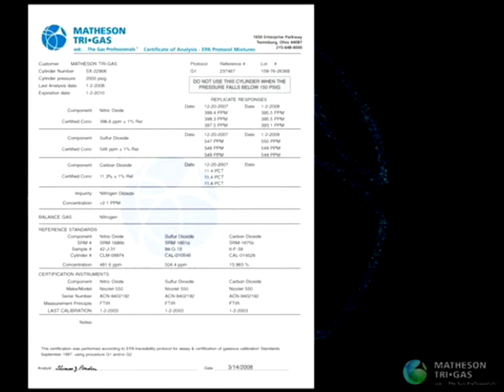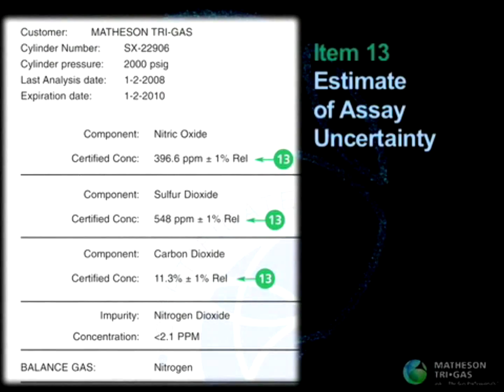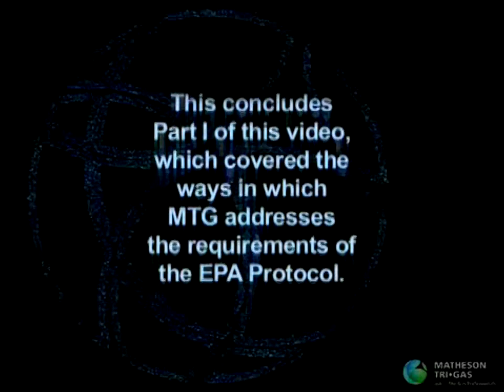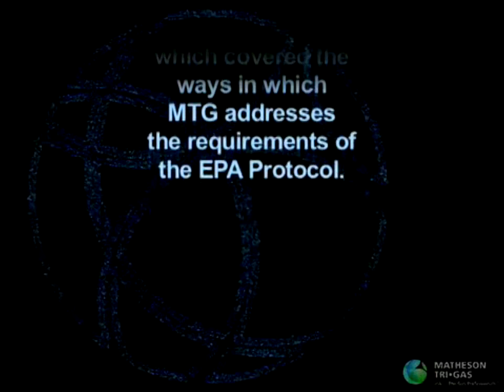Moving back up to the top of the form, the final required item is item number 13, an estimate of the total uncertainty associated with the assay of the candidate standard. This estimate must include the uncertainties of the reference standards, the analyzer multipoint calibration uncertainty, and any interference correction. At this point, we have completed the fundamental discussion and walkthrough of a typical certificate of analysis for EPA protocol mixtures and the ways in which Matheson Trigas complies with EPA documentation requirements.